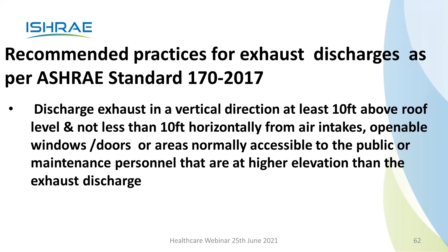This is a very small but important tip. You've got an infectious isolation room out here, and you've got the exhaust fan here. This part of the duct is positive, because the blower is here. So what happens if the duct is leaking? It gets into the occupied space. So this is the wrong method of doing it. The right method is that the entire ducting which is going over other occupied spaces has to be under negative pressure. This is the correct method.